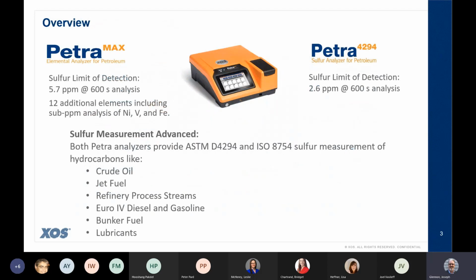All right, so just an overview. Again, we have the Petra Max and the Petra, both compliant with the ASTM D4294 and also the ISO 8754. With LOD, the Petra Max is 5.7 at 600 seconds, and the Petra 4294, the sulfur only, is 2.6 ppm LOD at 600 seconds. And the Petra Max has the added capability of 12 additional elements to sulfur, including nickel, vanadium, and iron, very of interest to the crude oil world, of course, at sub-ppm levels.